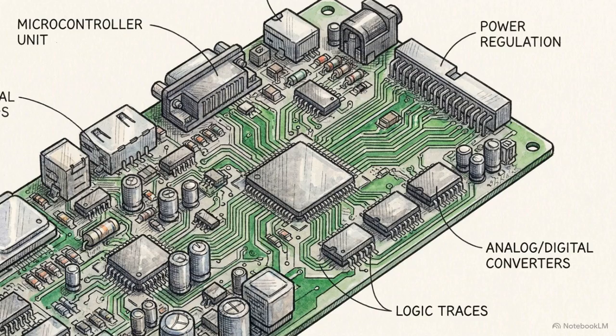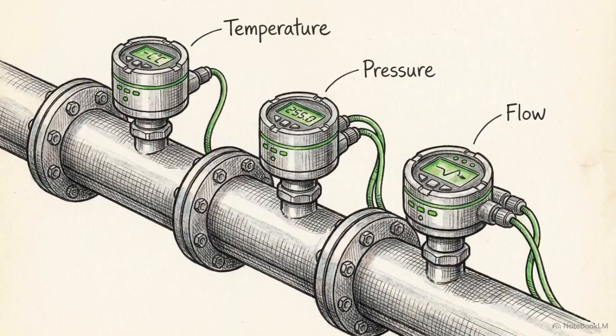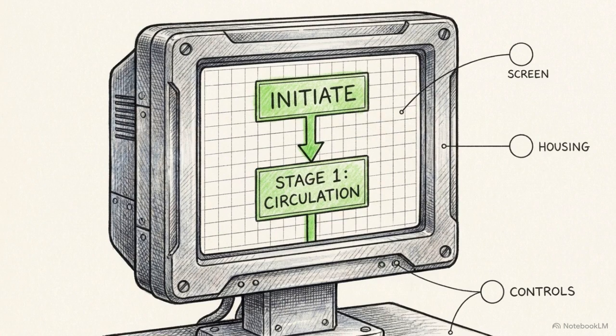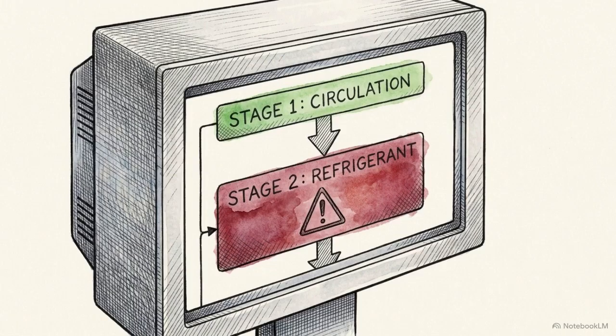Binding these mechanical components together is an invisible digital layer, the system's control logic network. Before the chiller is allowed to activate, a network of strategically placed sensors takes baseline readings of fluid temperature, line pressure, and internal flow rates. The logic operates on a strict fail-safe sequence. When the battery control unit sends a thermal request, the chiller first activates the pump. Only after the sensors mechanically confirm stable fluid flow does the system allow the compressor to initiate.